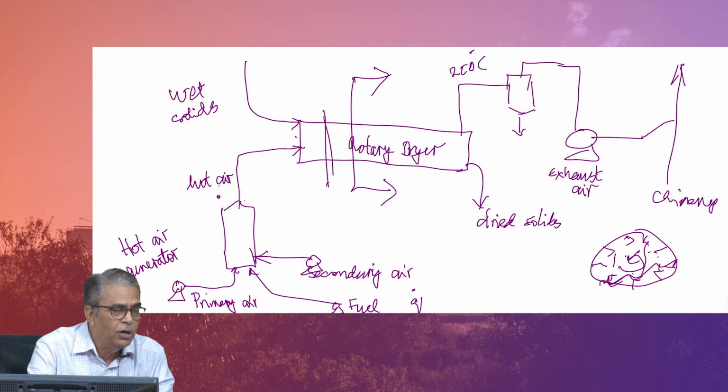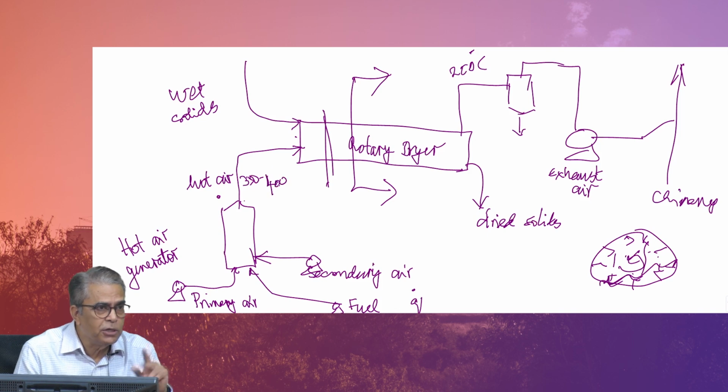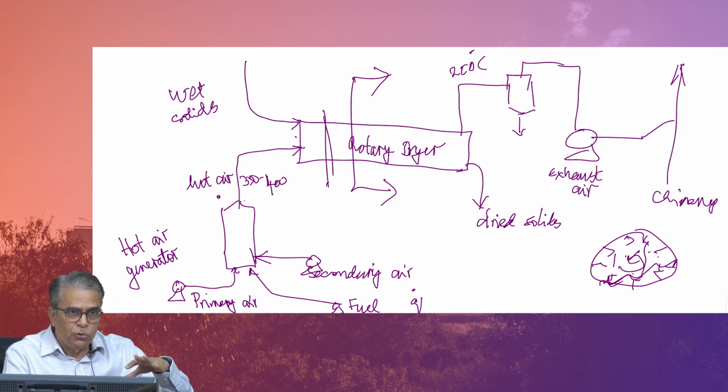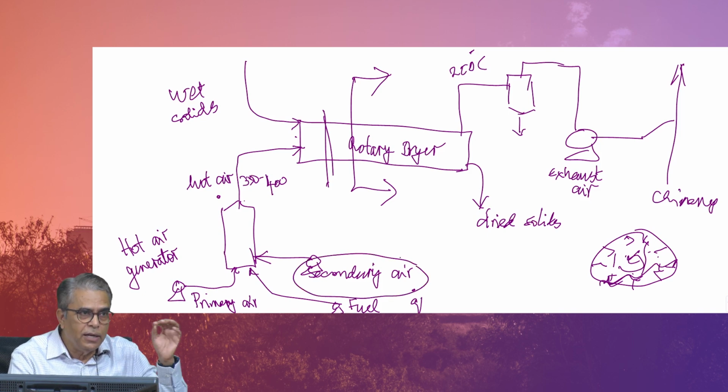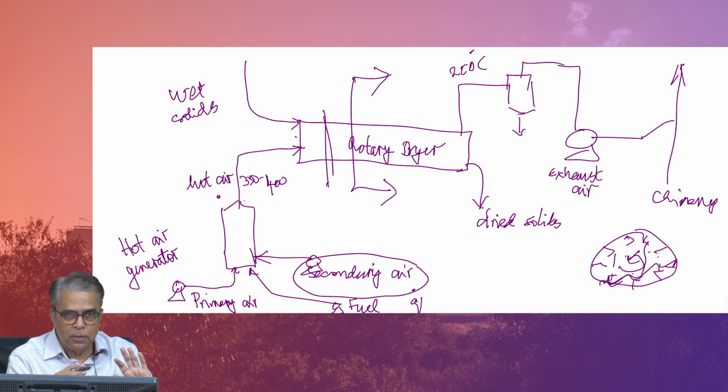Incidentally, it will also bring down the hot air temperature. So, usually in this case it is not relevant, but usually it will be of the order of 350 to 400. So, which means that if the 1800 flame temperature is brought down to 400, that is the amount of cold air you will add. Okay. Why this complicated description is, we are catching on the secondary air. Now, this word secondary air in the problem statement, now you can appreciate this is a lot of air. Let me conclude that way.